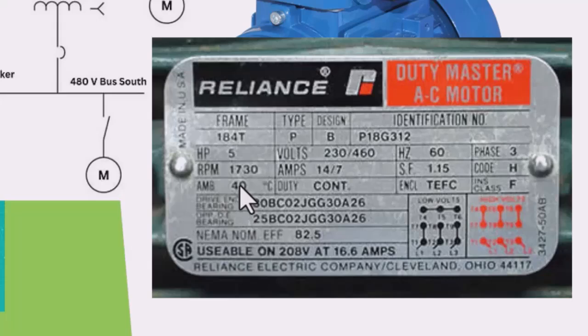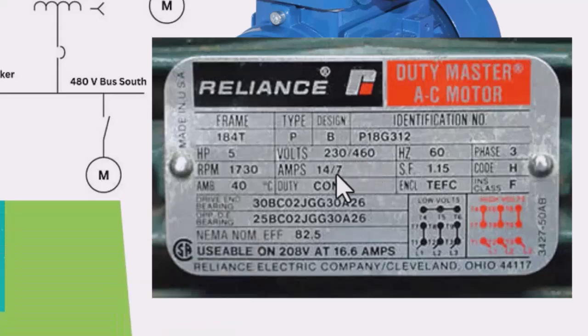You also do the same comparison. This is the power, okay. You also check the horsepower, to see that it matches what was specified on your specification sheet. This is your input voltage, I mean to say 230 or 460. So if it is something that will be installed here, it means that this voltage and the voltage at this bus should match. Then this is the amount of current that this particular electric motor will be drawing on the circuit, okay. So if it is running on 230, this is the amperage. If it is running on 460, this is the amperage, and this is the frequency, and this is the phase. So all of these you check, to see the speed, the RPM, the AMB, and the duty, which means that it can be used continuously.